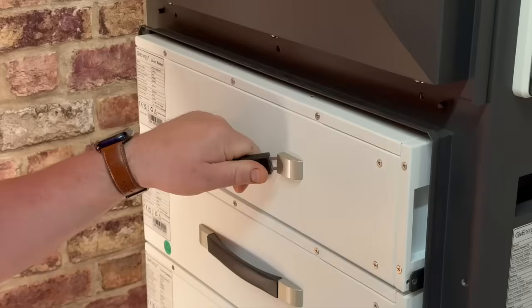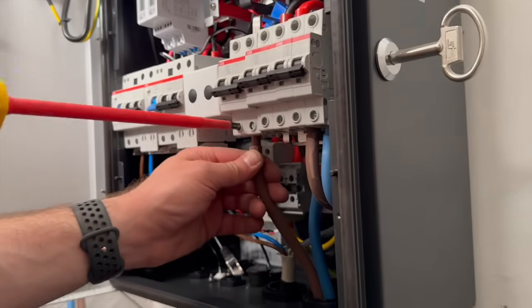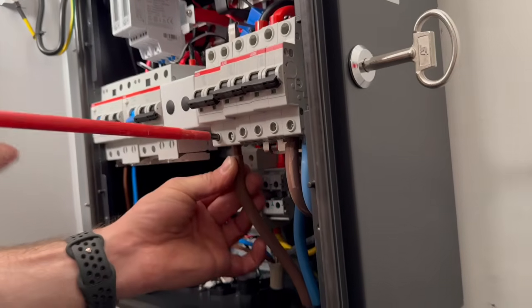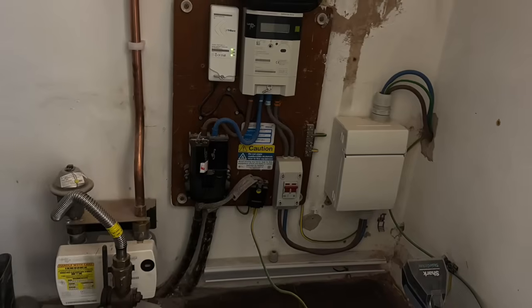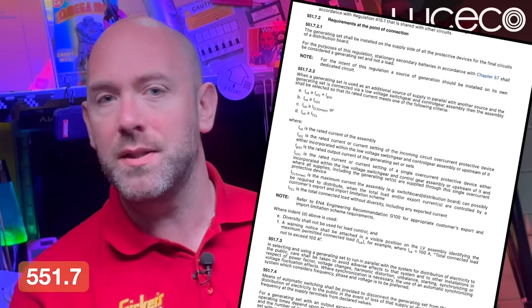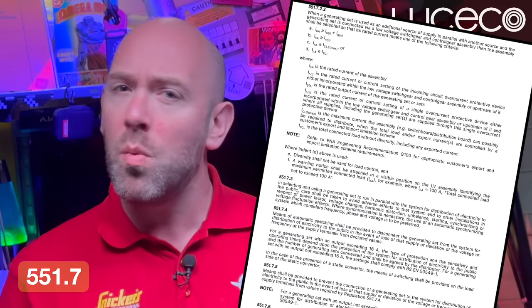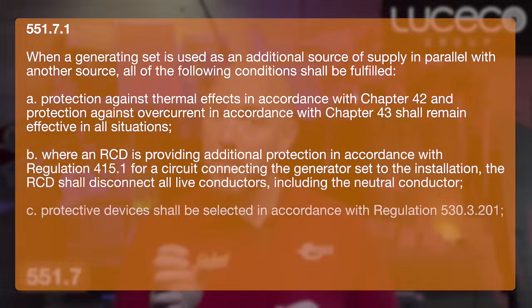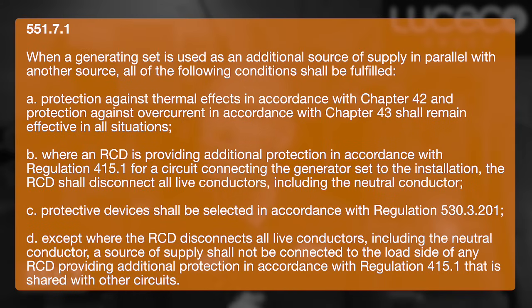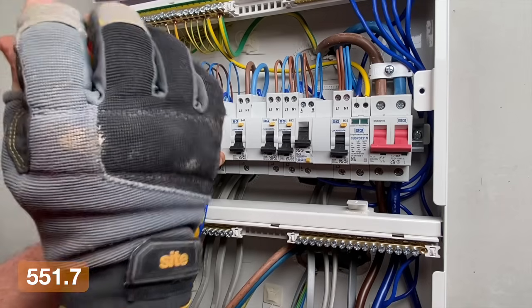Solar PV, battery storage, multiple sources of supply, all connected into the same system. So the installation is no longer just receiving power, it is interacting with it. And that has a direct impact on how the system behaves under fault conditions, including earthing systems like TN-S, because the way the system responds can now depend on the direction of power flow. And this is where Regulation Group 551.7 comes in. This has been redrafted to deal with installations operating in parallel with other sources, and the key requirement now is that protection must remain effective regardless of the direction of power flow. So it is no longer enough to design protection for one direction, it has to work in both.